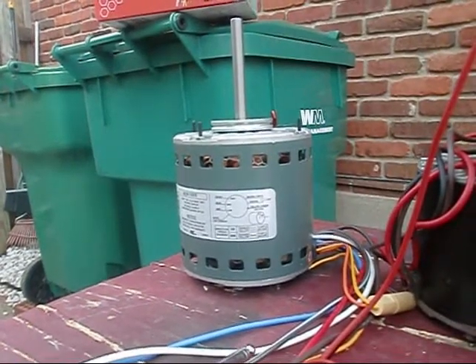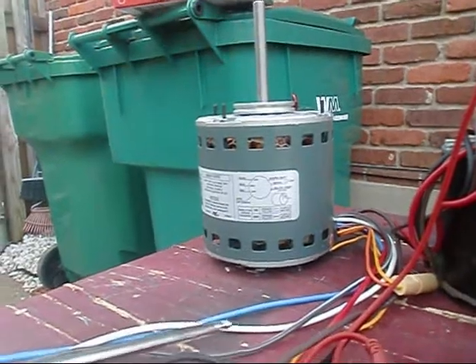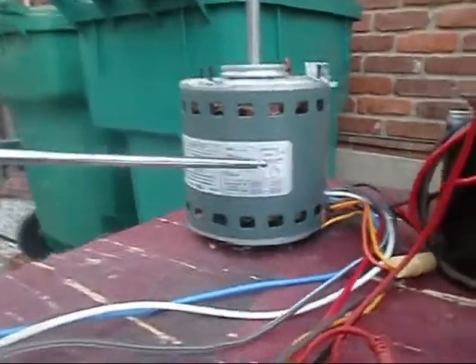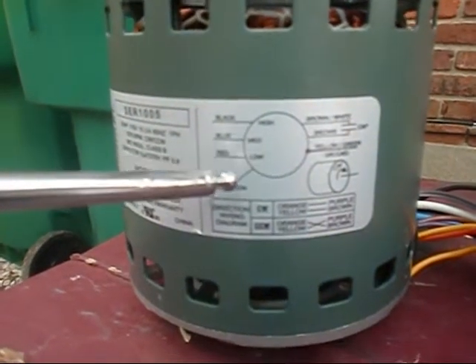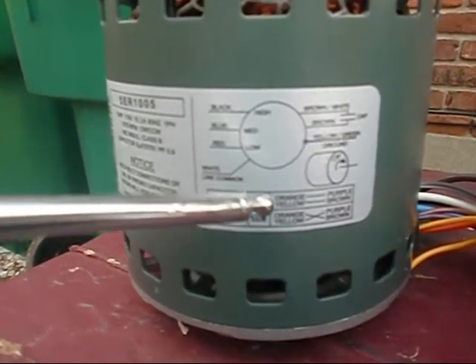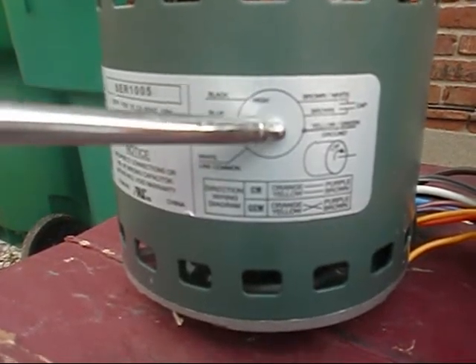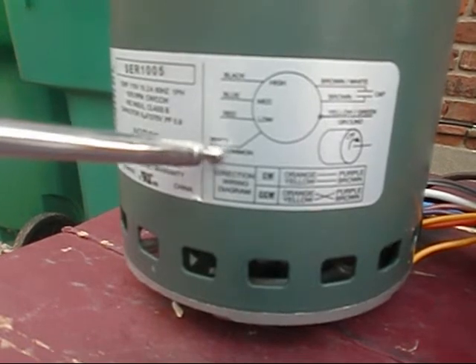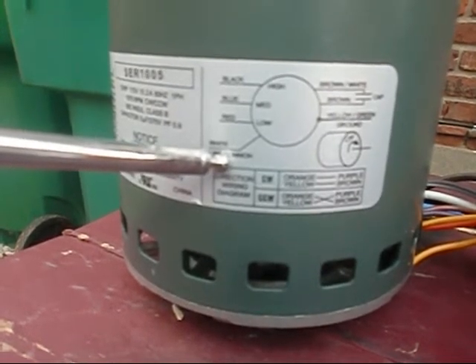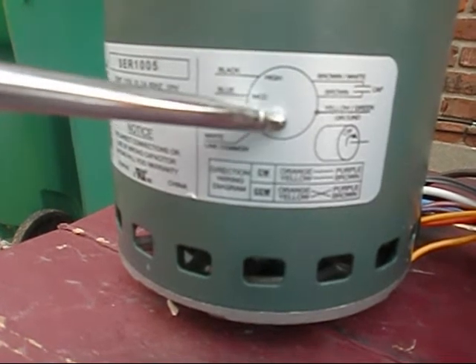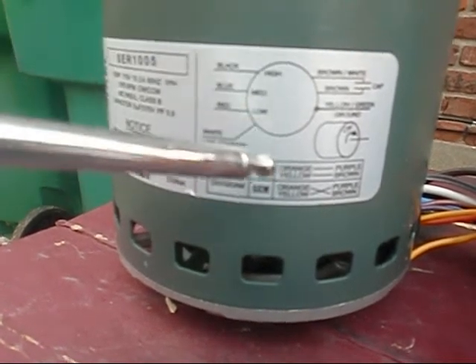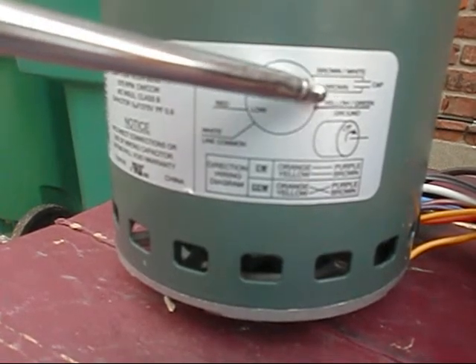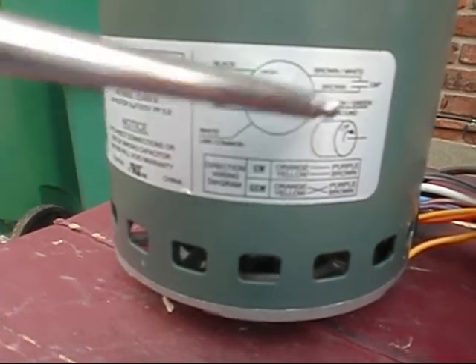What she is, she is a 115 volt half horsepower 1075 RPM motor and multi-directional. And what we did last time is we actually shot a little video and we determined what would be common to run, common to start and start to run. I actually looked at our exploded view we have right here and we see that on our drawing, white is line common, red is low speed, blue is medium speed, black is high speed. Our brown and white and our brown join into our cap, our yellow and green is our ground.